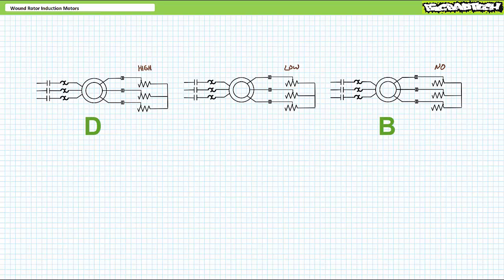Unlike the bank of fixed starting resistors intended for intermittent operation discussed previously, if the variable resistors are designed for continuous operation, this configuration — sometimes known as a regulator — also allows a primitive means of speed control.